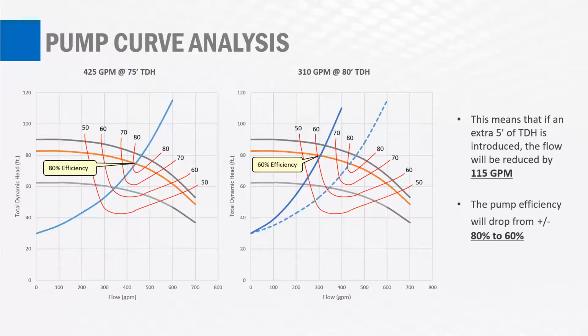In addition, you can see that the pump efficiency has dropped. We thought it was going to be operating at 80% efficiency, but now with just 5 feet of extra head, it's operating at 60% efficiency. Think about all of the times that this pump is operating at that lower efficiency, and the extra power consumption and associated cost of that power.